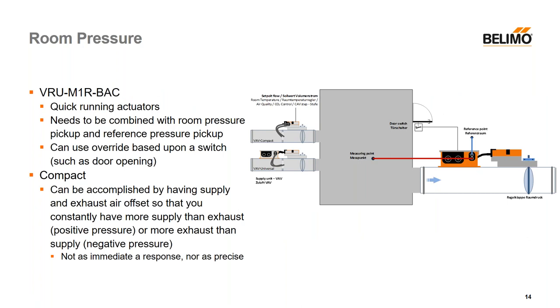Moving on to room pressure: our recommendation is to use the VRU-M1R-BAC in combination with a quick-running actuator. Same as the duct pressure application, you need a reference pressure pickup in an area where pressure isn't fluctuating, and instead of a duct pressure pickup you'll need a room pressure pickup. A nice feature of this product is a built-in override — for example, if a door is connected to a switch, you can prevent the actuator from moving and chasing a pressure measurement just because of a door opening, avoiding unnecessary cycling and reducing actuator wear.